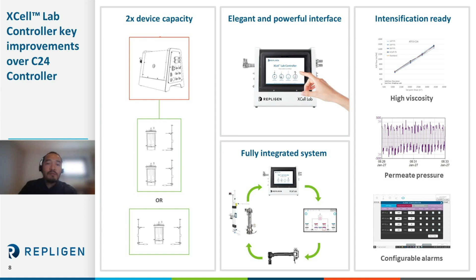As I've said before, the new XCell Lab controller is based on an improved control platform. Actual flow is measured using a state-of-the-art flow sensor, and is therefore inherently more accurate than the old C24 controller, which relied on a time-based algorithm to deduce flow rates. With certain processes that have challenging cell culture conditions, such as high viscosities, maintaining accurate ATF flow rates can be challenging, and has been so with the C24. But as you can see from the data on the right, the XCell Lab is able to maintain consistent flow rates with increasing viscosity in a linear fashion and with high precision. Basically, the overlapping lines indicate a high correlation between theoretical and observed flow rates.